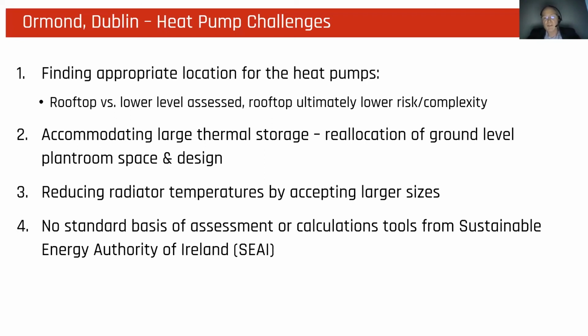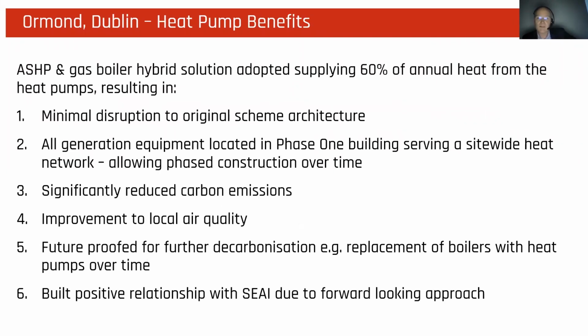FairHeat worked with us with Sustainable Energy Ireland, and we made a presentation to Sustainable Energy Ireland, and they allowed us to change the calculation. And so the standard base of the calculation, they accepted thermal storage, and they've now changed. So Ormond is one of the first projects in Ireland to have no CHP, no PV, and thermal storage with air source heat pumps as the basis of the calculation, and they were very impressed with it. So I think you'll see more of that in Ireland. Next slide, please.